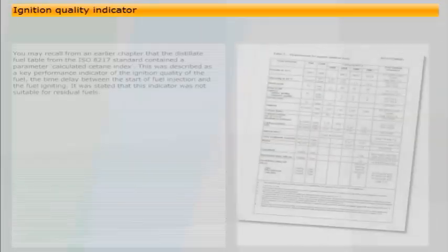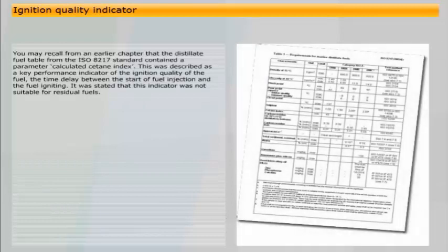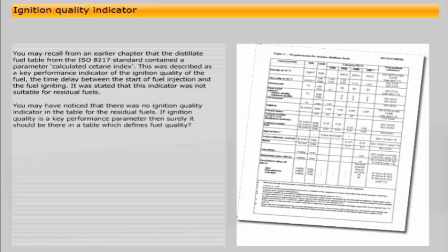You may recall from an earlier chapter that the distillate fuel table from the ISO 8217 standard contained a parameter called calculated cetane index. This was described as a key performance indicator of the ignition quality of the fuel, the time delay between the start of fuel injection and the fuel igniting. It was stated that this indicator was not suitable for residual fuels. You may have noticed that there was no ignition quality indicator in the table for the residual fuels. If ignition quality is a key performance parameter, then surely it should be there in a table which defines fuel quality.